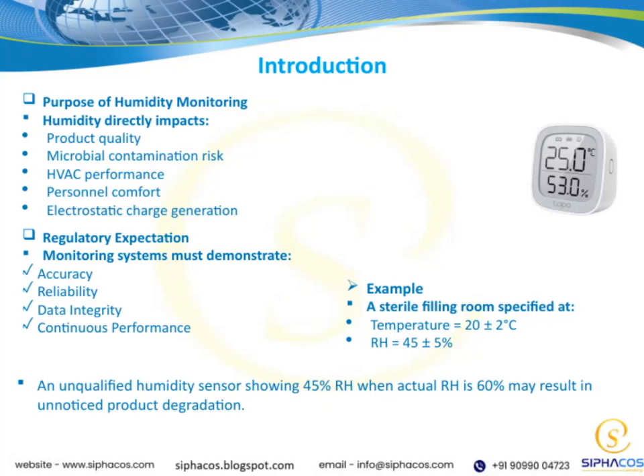Let's talk about why accurate humidity monitoring matters. Imagine a sensor reads 45% relative humidity, but the actual level is 60%. That gap might seem small, but it can lead to product degradation going unnoticed. In a sterile filling room, where temperature and humidity are tightly controlled, even slight errors can affect product quality, increase contamination risks, and impact HVAC efficiency. Regulations expect monitoring systems to be accurate, reliable, and continuously performing, with data integrity you can trust.